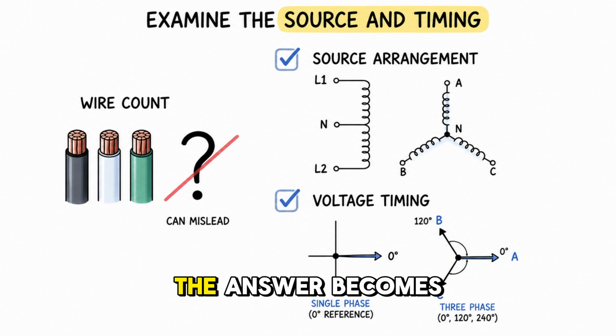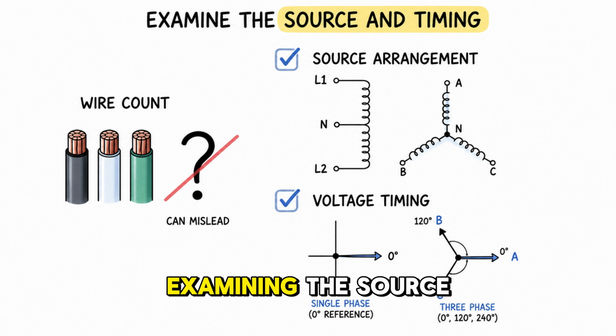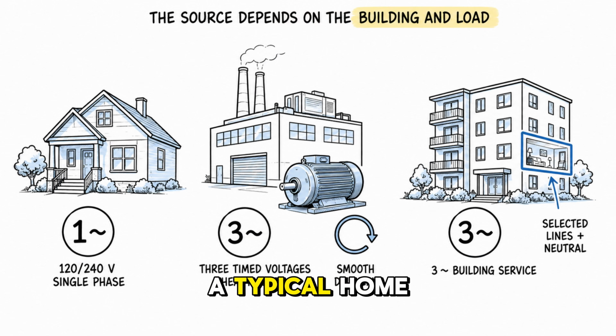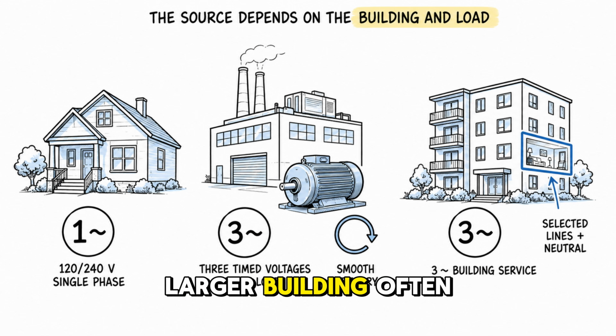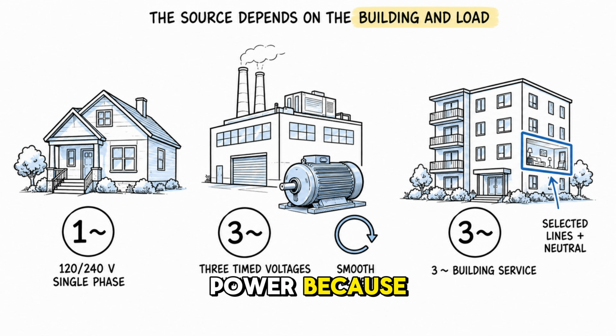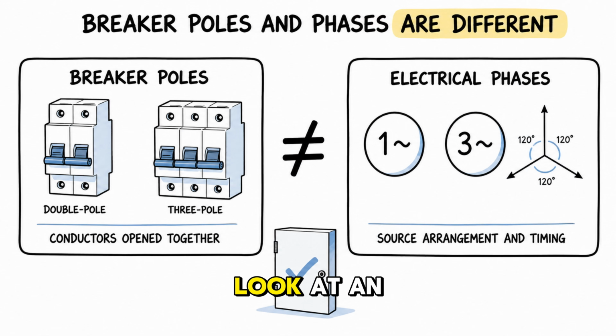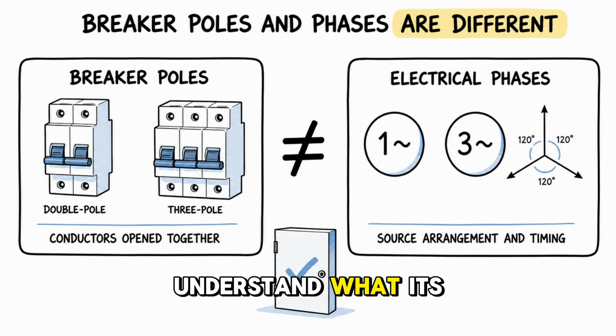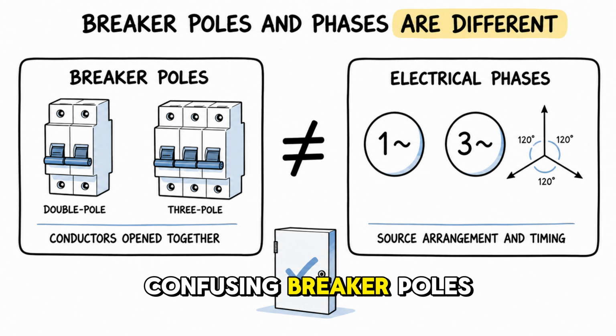The answer becomes clear when you stop counting wires and begin examining the source and timing. A typical home receives 120 and 240 volts single-phase power. A factory or larger building often receives three-phase power because three-timed voltages supply heavy loads more smoothly. An apartment may receive only part of a larger three-phase system. You can now look at an electrical panel and understand what its breakers are doing without confusing breaker poles with electrical phases.